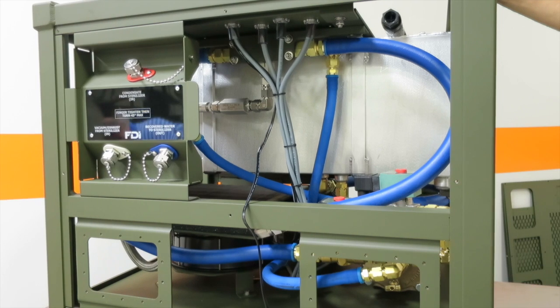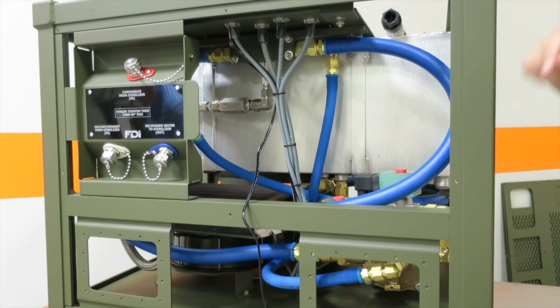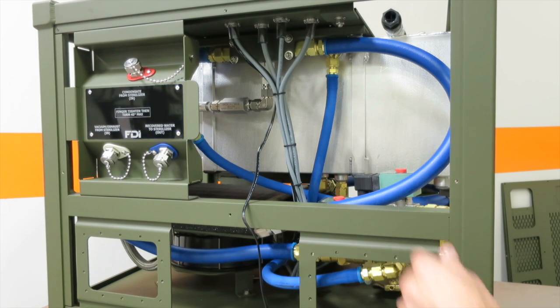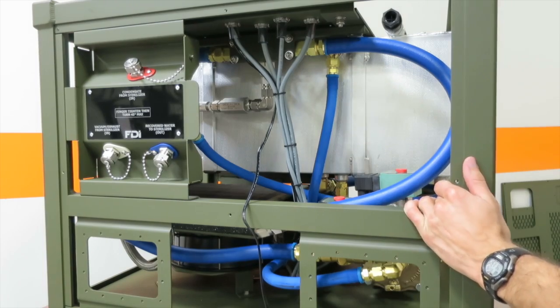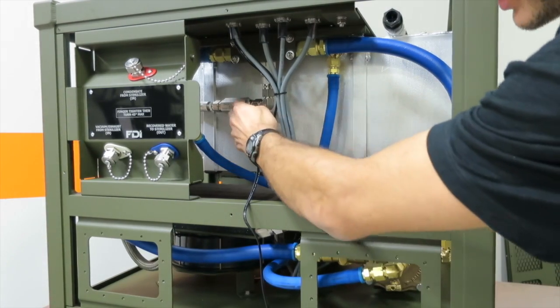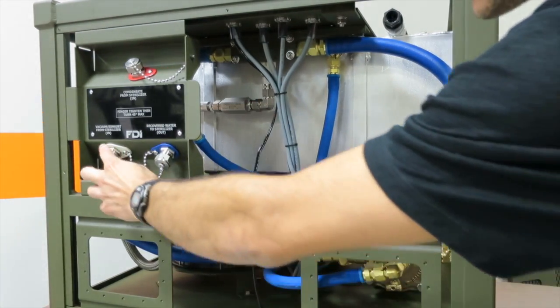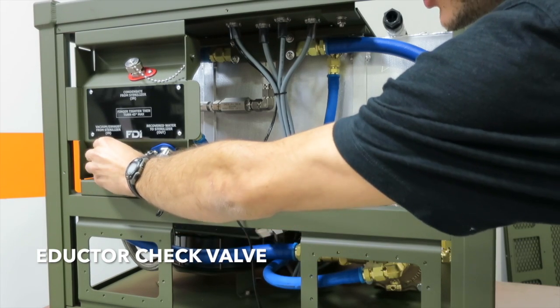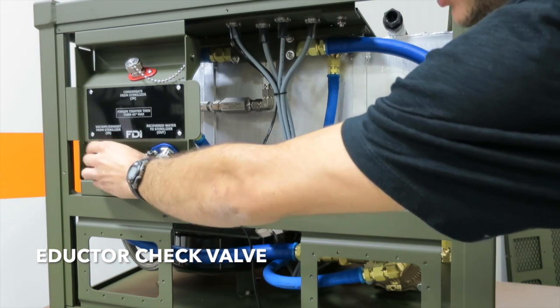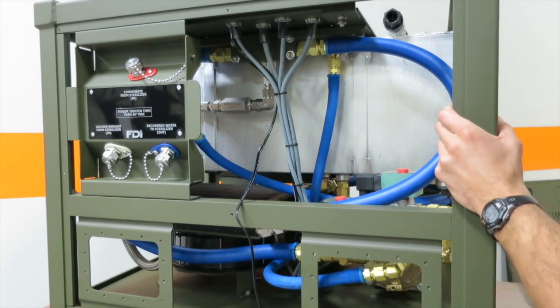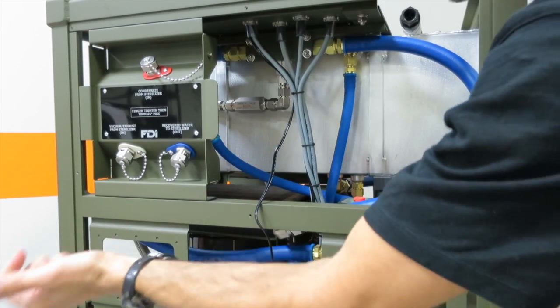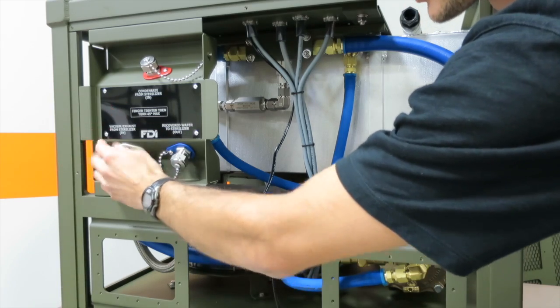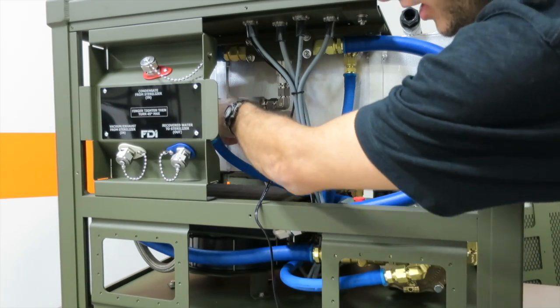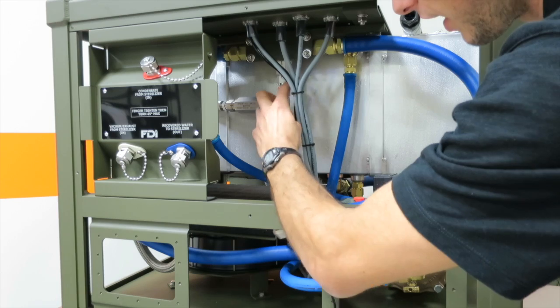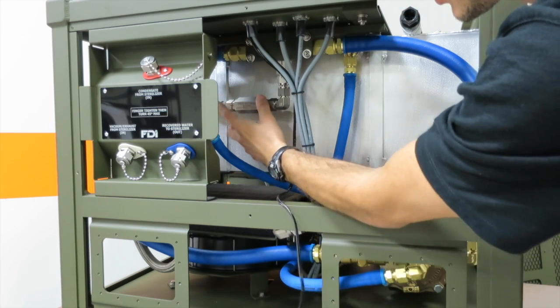Alright, so now we're talking about the left side of the water recovery system. The first component we're going to talk about is the EDUCTOR check valve. Right here you have the vacuum exhaust from the sterilizer. That's where that hose connects. Anytime the water recovery system is pulling a vacuum on the chamber, all that steam and air and condensate is going through this check valve and then into the EDUCTOR.